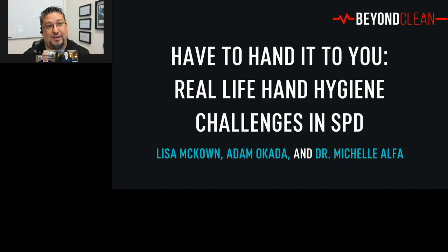So when we're talking about this issue, you have decontamination, which is essentially removing visible and non-visible soil. You're physically removing it with enzymatics or detergents that make it easier to get that soil off, but it's just removal of soil. Those microorganisms, those microbes, are still present on the device after that. It's not killing those microbes and it's not removing them—you're removing the gross soil. So that's what the disinfection step does.